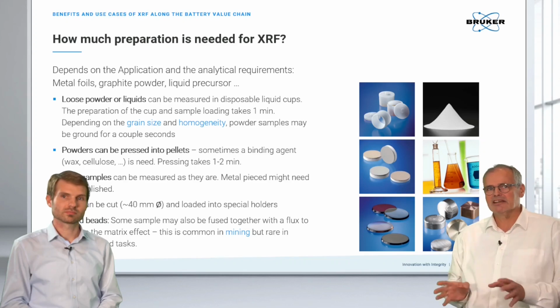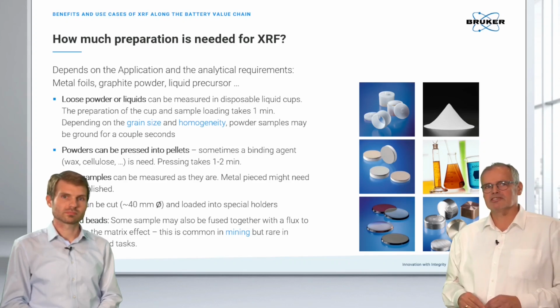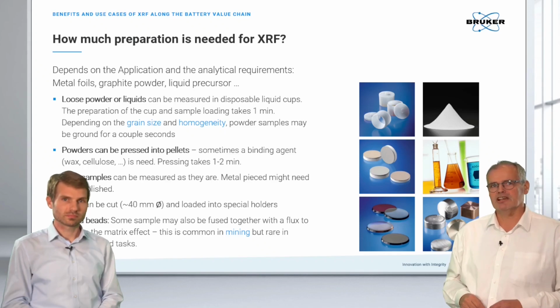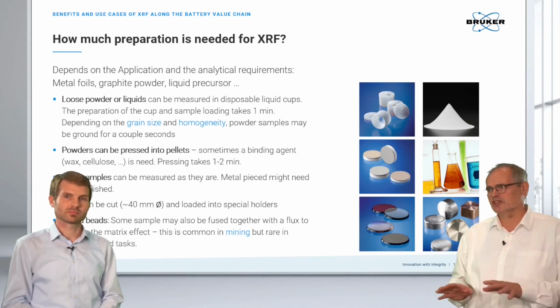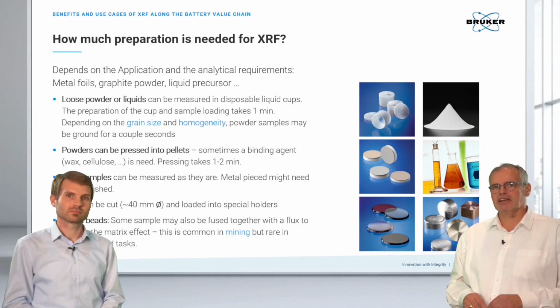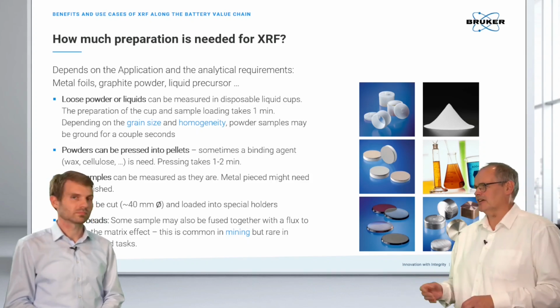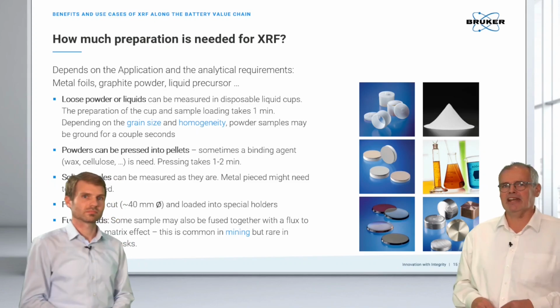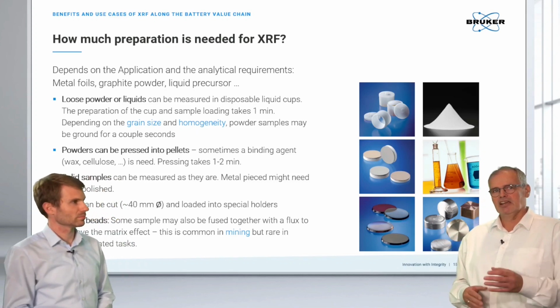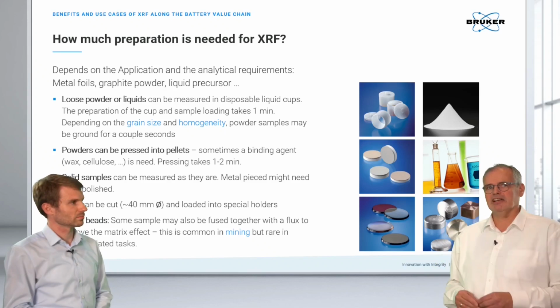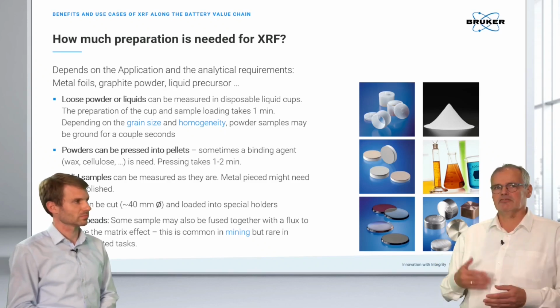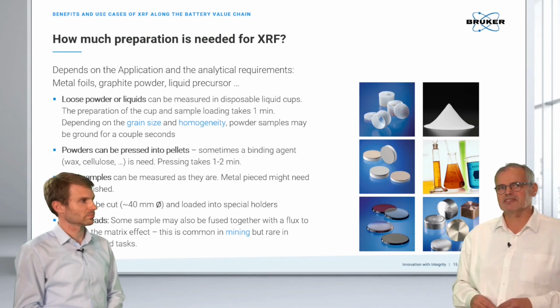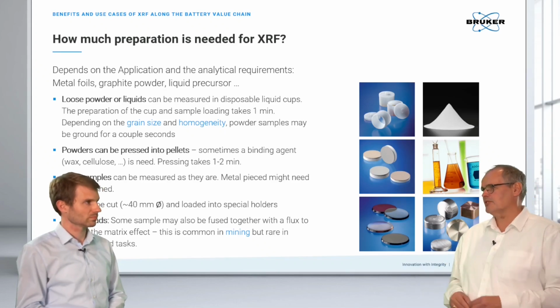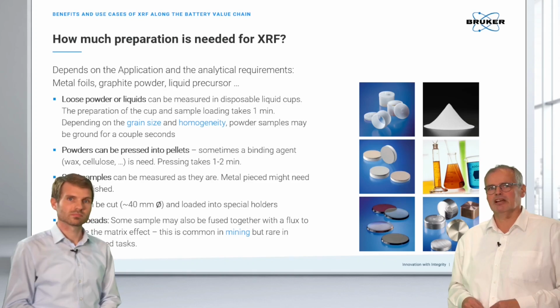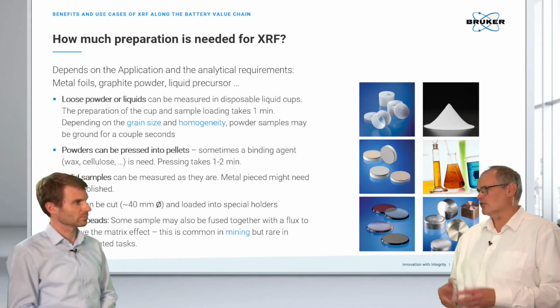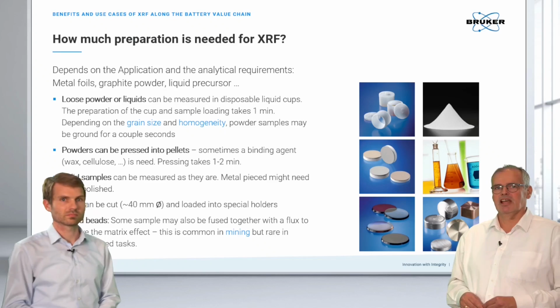So there are some pros and cons. The one thing is the grain size can have an influence. Also, homogeneity might be a factor, but nevertheless, that's a very quick, easy way. You fill the powder or liquid in and analyze in the instrument. If we want a little bit higher intensity and sensitivity, if we want to be more representative with the sample, we press the powder with a little bit of binder after grinding into a stable pellet. Those can be stored also for years.